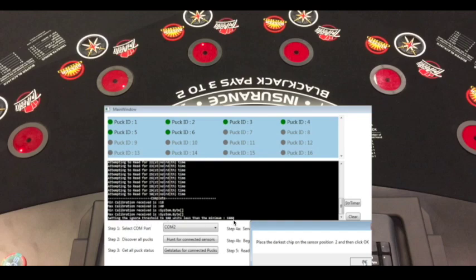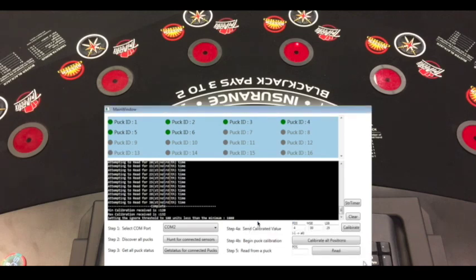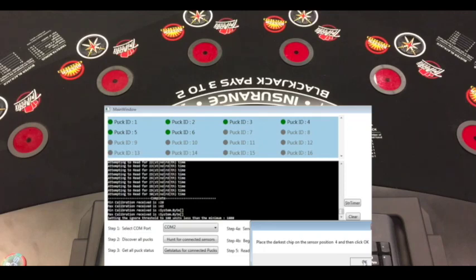So really all we did is we set that sensor number 1 to 900. Anything we put on that sensor that doesn't read above 900 won't activate the sensor. But anything we put on there that reads over 900 will. And all of that is built into the default config. Same thing with sensor 2. We just hit OK. It came back with a minimum reading of 120 and a max reading of 130. We set it to the same, 100 units less than 1,000. Do the same thing for 3, same thing for 4, 5, and 6.